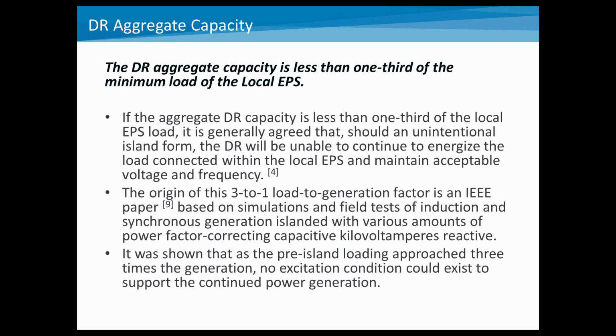So first off, that requirement that you would be able to meet the requirement if the DR is less than one-third of the minimum load. Basically, what this means is that the DR size is relatively small with respect to the local load. There are a couple of references and work that's been done looking at this kind of ratio, sort of 3-to-1, which is pretty high, showing that you would not be able to maintain a stable island operation for both induction and synchronous generators. It basically showed that in the pre-island condition, when the load is approaching three times the generation, you can't really support the load. And this is a key thing that is often difficult to determine: what the actual loads around the distributed generation are. But basically, this is saying that if you have a small DR in relation to the load, you won't be able to support an island condition.